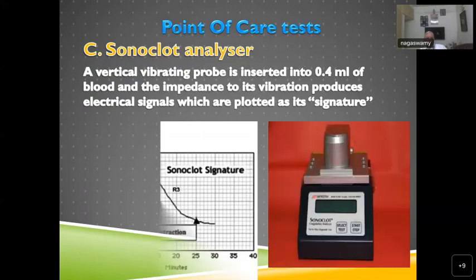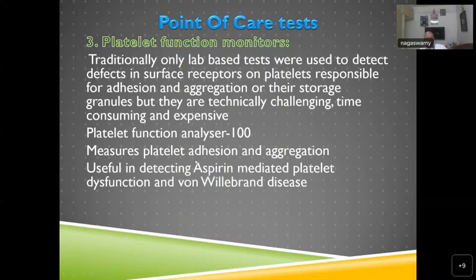Sonoclot is another newer device — a vertically vibrating probe is inserted into only 0.4 ml of blood. The impedance of its vibration produces the clot signature — a distinct waveform. This can be asked in OSCEs where you identify the Sonoclot signature. Parameters include R1, R2, R3 times, clot retraction, and clot rate.